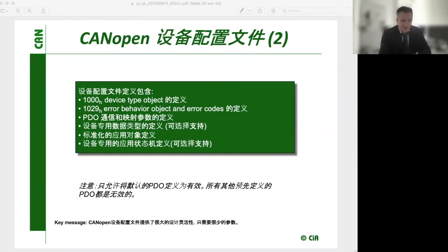So the first parameter you should know is this mandatory CANopen parameter for any CANopen device, but in 402 it is specific because it contains a very specific point. We talk about this in the next slides. Besides it, standardized is the error behavior in CANopen, and there are special errors, drive errors, not only CANopen or network errors, but drive errors, for example, the drive is stopped or the drive is in an error condition because the magnets are actually without current and so on.